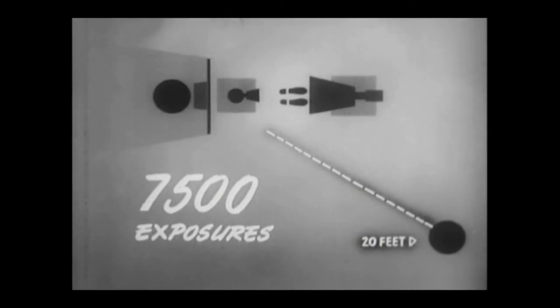However, behind a lead screen or at a distance of at least 20 feet, the person would not exceed three-tenths of a roentgen per week until after 7,500 exposures were made.